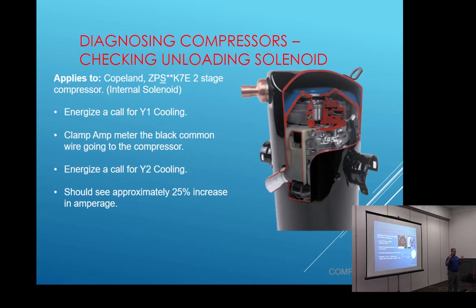For all our 2-stage equipment, I've had calls here, had a couple of one here a week or two ago. It says, Mike, I got a 105-pound suction and a 250 discharge, and it's just not cooling right. I can't get my temperatures and pressures right. I said, well, it's 2-stage. He says, yeah, I got a call for Y2. I said, well, is the solenoid pulling in? Well, I got a call for Y2. Well, how do you know the solenoid is working?